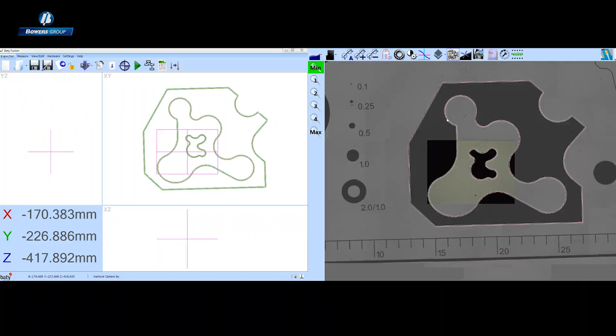The problem with camera-based systems in the past has been the limited field of view means that we can't see what that overlay and image fit looks like. The big advantage with the latest generation of Fusion software is that we can stitch our images together. This is my current camera view, but if I roll out on the mouse and zoom out here, we can see that actually I have a picture of the entire part that I've measured, because every time we've been to a position, we've saved that image and connected them all together, stitched them all together to give us a larger saved image. Now, on top of that image, I can use this feature, overlays, to show other information on top of the stitched image. If I select DXF, you can see I can bring in the DXF here, and I can see that all of the features now fall within my tolerance band.